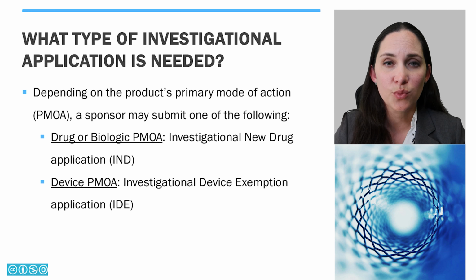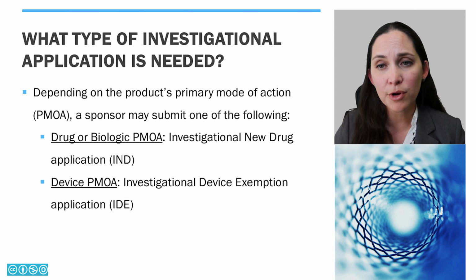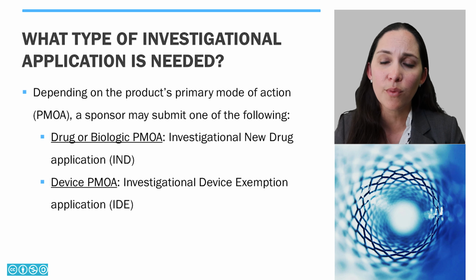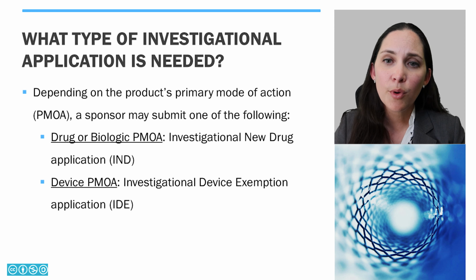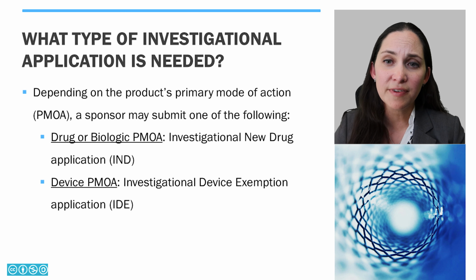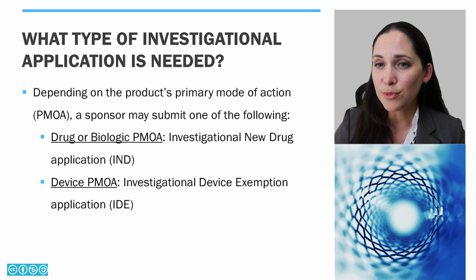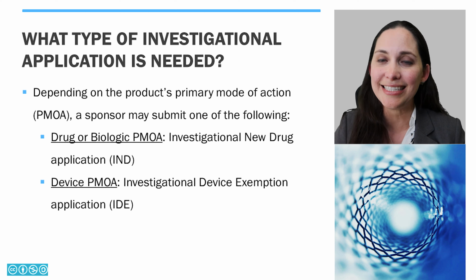So the next question is, what type of investigational application is needed for each of these combination products? Depending on the product's primary mode of action, a sponsor may submit one of the following. If the PMOA is a drug or biologic, it would make sense to submit an investigational new drug application, or IND. If the PMOA is more of a device, FDA would prefer that you submit an investigational device exemption application, which is also known as an IDE.